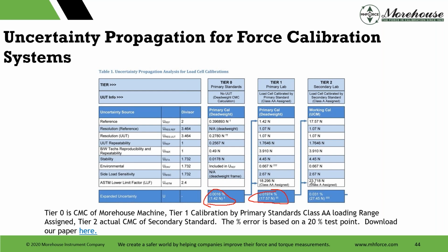And then if we took that load cell and said, okay, now I'm going to use that load cell to calibrate something else, and I'm going to do all this stuff again, you can see some things got larger. We kept repeatability the same. There's some things specifically that would get a lot larger than what are here. What we purposely did in the paper is we said, okay, let's make assumptions that this is the best load cell and that our repeatability and reproducibility stayed the same. However, we have to carry that uncertainty for the reference. And when we do all that and ran the calculations, we got a number of 0.03 for the 20% point.